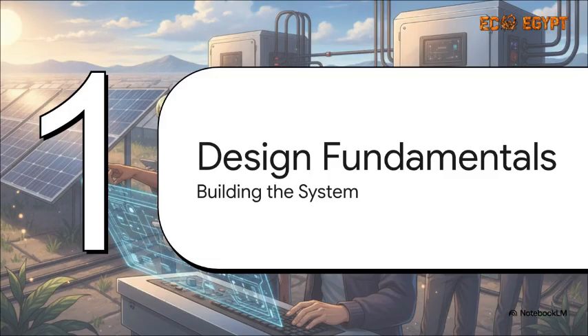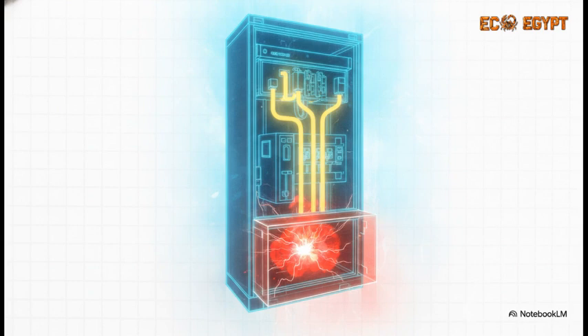Moving on to Section 2, Design Fundamentals: building the nervous system. Before a single piece of metal is even cut or a wire is run, engineers have to sit down and calculate some highly interdependent critical design parameters, starting with the rated voltage. This typically operates anywhere between 11 and 33 kilovolts, and that dictates the insulation levels and equipment clearances. Then we've got the circuit breaker current rating, which obviously must safely carry the massive AC currents generated by the inverter output. But here is where it gets really intense: the short circuit level. The switchgear's short circuit withstand rating has to safely handle massive calculated fault levels. We are talking about surviving 25 kiloamps of pure destructive force for a full second. That is no joke. Finally, you have to ensure proper protection coordination so only the faulted section trips, alongside totally seamless grid integration for things like anti-islanding and safe reclosing.